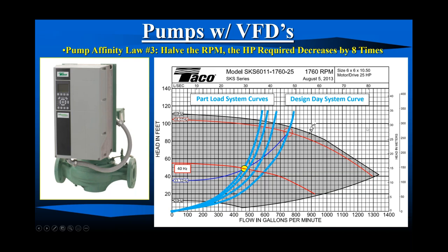And again, we can only perform where the system curve and the pump performance curve intersect. So now we're there. I don't know what hertz that is, but it's higher than 40. Is that a big deal? If you're in the energy efficiency business, it's a very big deal. Not because I say so, right? But because pump affinity law number 3 says so.